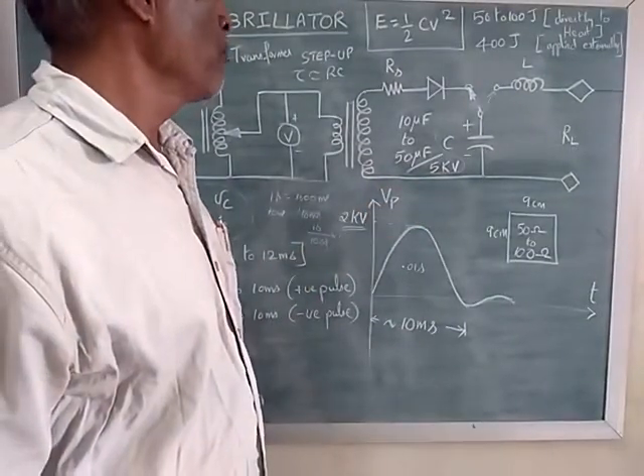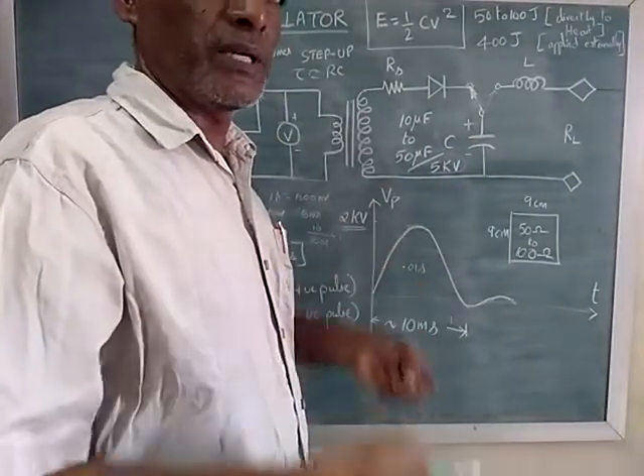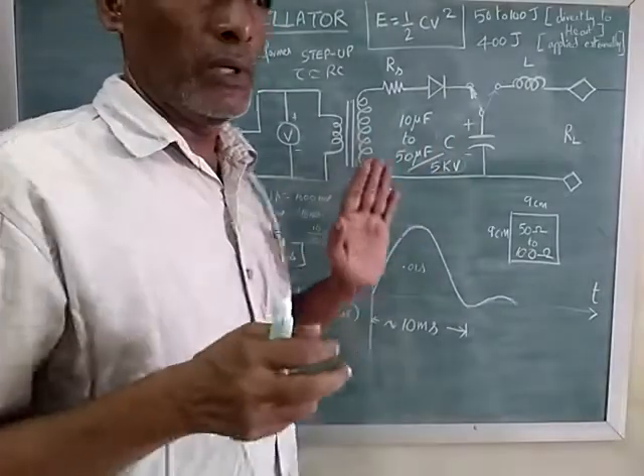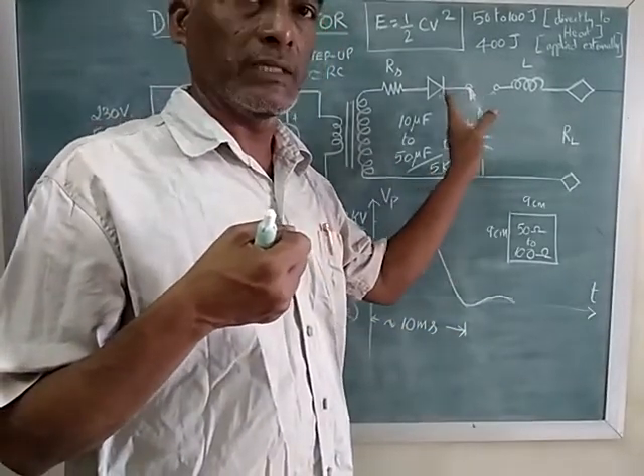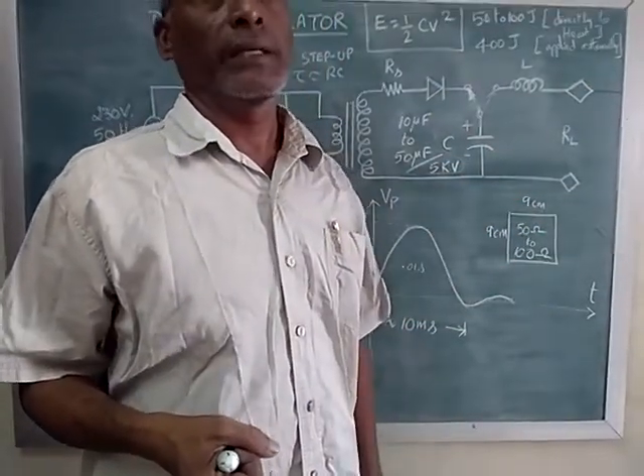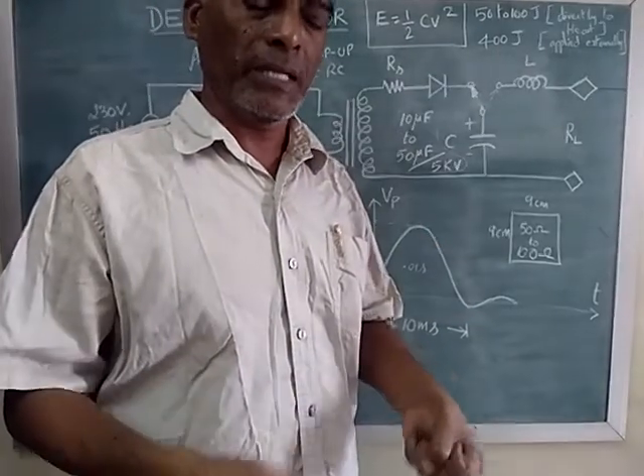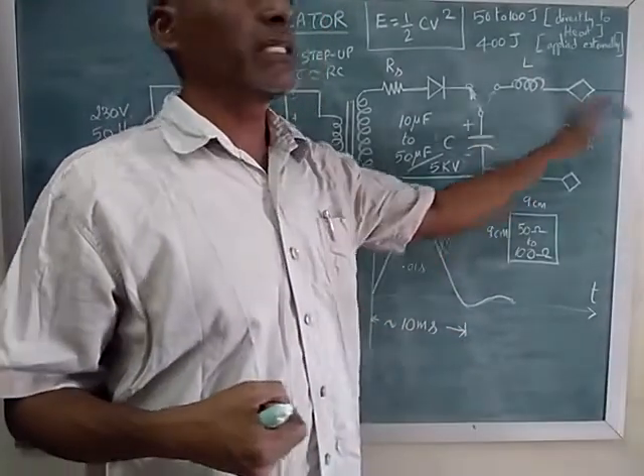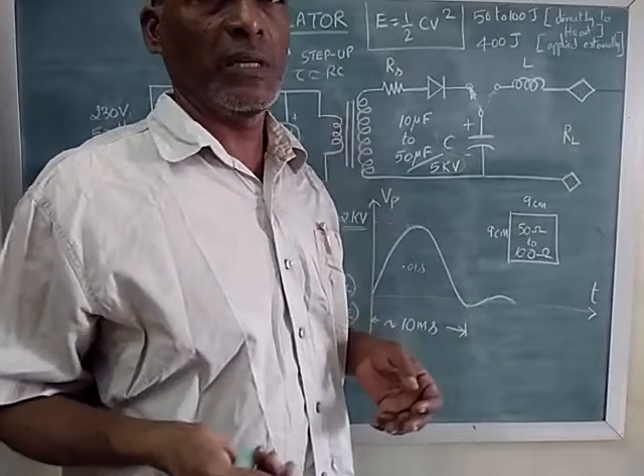So this is the shock that we are giving to the patient who has suffered cardiac arrest. So I told everything, this is the charging part. So first they will press, then release, press, release. That means during release, first they will press because charge, discharge. Then they will release and the connection will go like this. It charges once again, they press, they release the energy to the patient. Likewise, it is not continuously press, press then release, then once again press, release. Because the voltage across the capacitor, when it gets discharged completely, once again it has to be charged up. So it will charge very soon. It is also in the order of milliseconds only.